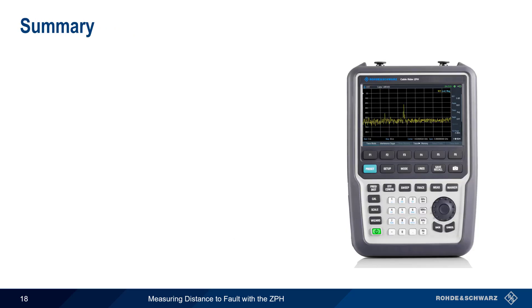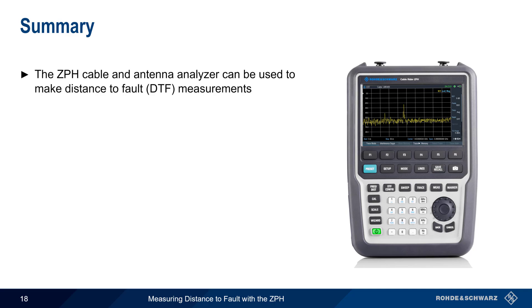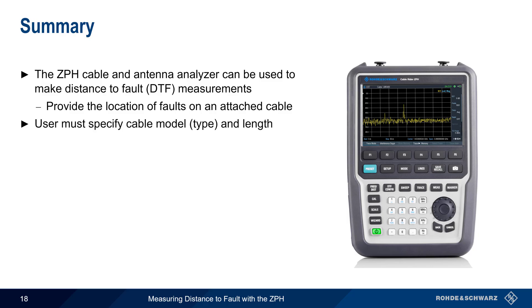Let's end with a brief summary. The Rohde & Schwarz ZPH cable and antenna analyzer can be used to make distance-to-fault measurements, and these provide information about faults on an attached cable. These faults are typically defined as return loss less than a user-specified value. In order to perform a distance-to-fault measurement, the user must specify a cable model or type of cable, as well as the length of the cable. In addition, the span and center frequency of the measurement must be given, although span can be determined automatically by the ZPH.